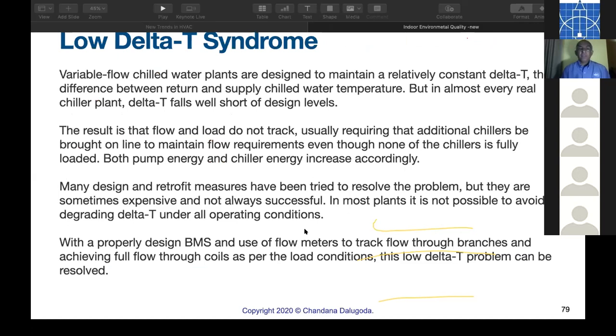We design for 7/12 operation, we commission, but a couple of months later, we find, sometimes, not always, delta T becoming low and low. What is the problem? Especially variable flow chilled water plants are designed to maintain relatively constant delta T, the difference between return and chilled water supply temperature. But in almost every real chiller plant, delta T falls well short of design values. The result is that the flow and load do not track.